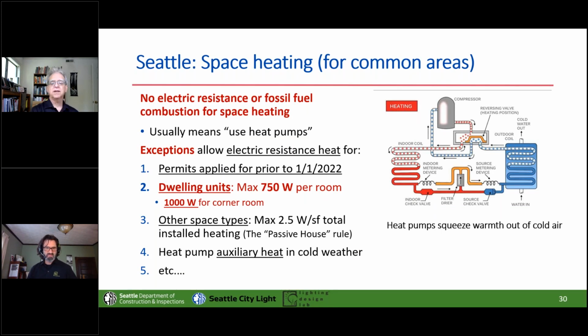Well, I just wanted to get back to that rule that we have in the code that says you've got to not use electric resistance or fossil fuel. So you're going to use some kind of heat pump, and for the common areas, you'll need to do something like a larger scale heat pump system. But as we mentioned, for the dwelling units, you can do that electric resistance if you so choose. So it gets complicated. There are lots of allowances for small loads and for very cold weather. Just keep that in mind.